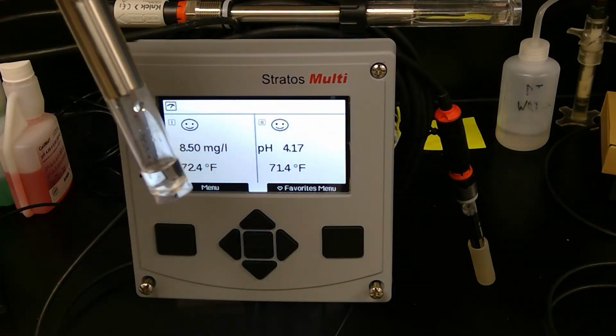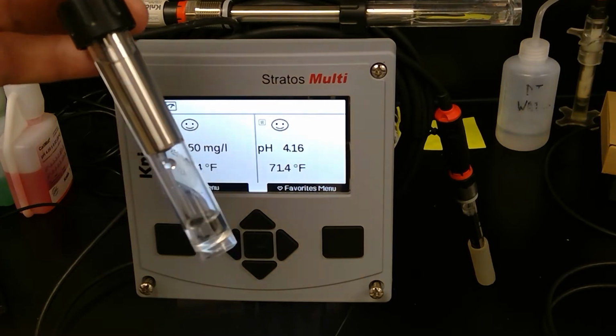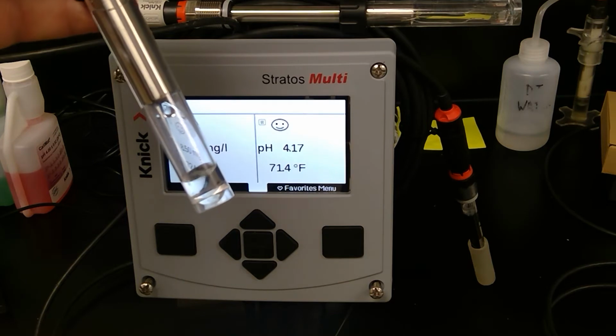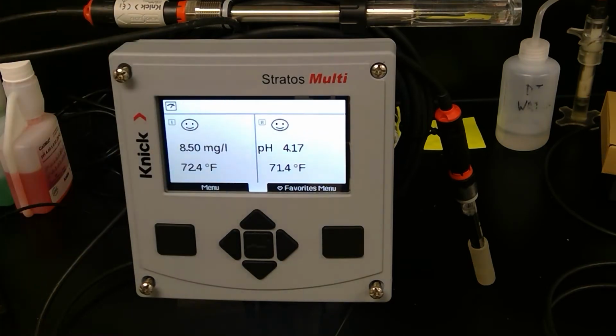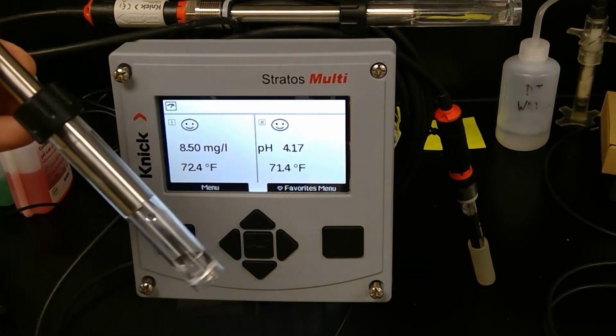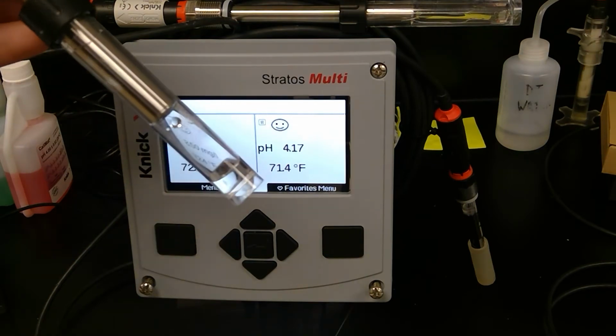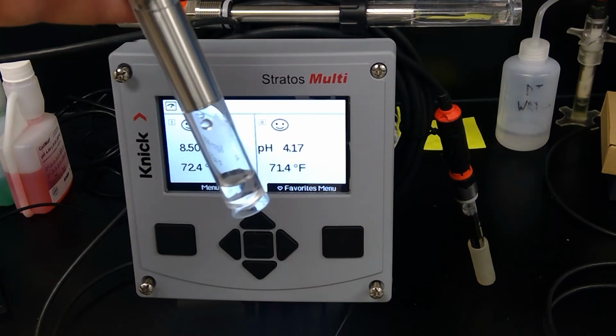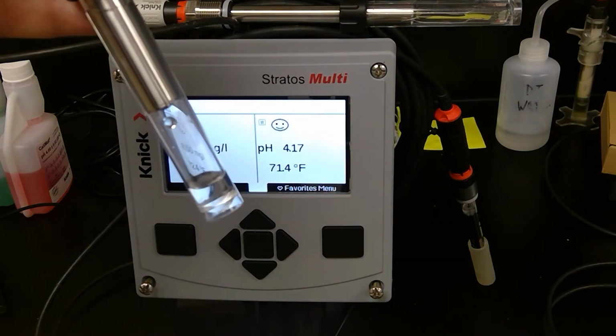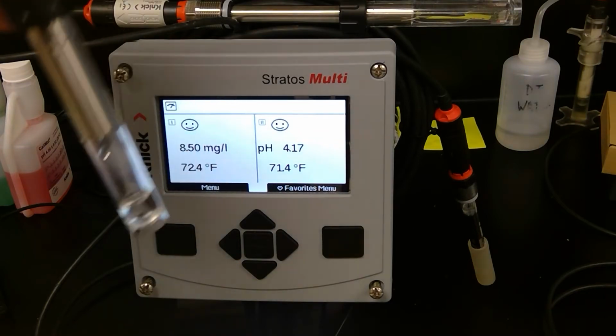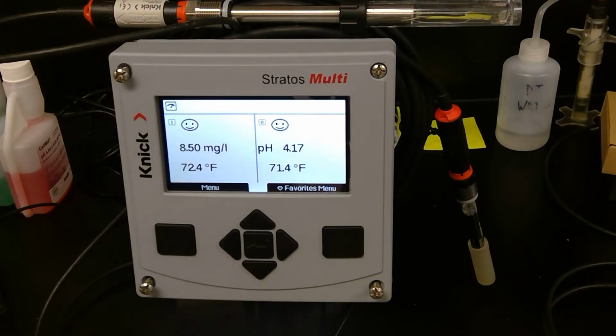You also notice that it's installed in a calibration beaker with a little bit of tap water in the bottom. I'll talk about why we do that. The reason is that when we go into the calibration, we want to make sure that it's in a 100% relative humidity environment. By putting it in this beaker with a little bit of liquid, without the sensor membrane touching the liquid, after about 15-20 minutes, you can be assured that it's in a 100% relative humidity environment.